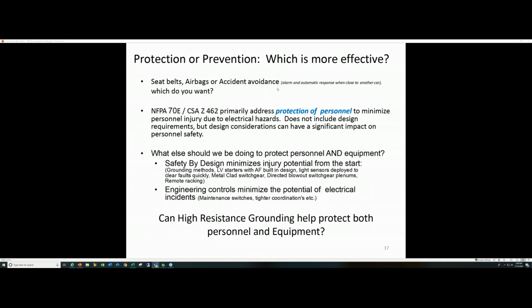And you could also employ engineering controls to minimize the potential of electrical incidents. For instance, maintenance switches, tighter coordinations. We call them maintenance mode switches, that you would activate if you were interacting with the equipment and taking it to a lower instantaneous current while you're interacting, so the incident energy is reduced. So that's something you can do. And most of you guys are familiar with all of this. The other thing that can be done is, well, what about high resistance grounding? How can that help protect not only the employees, that guy on Christmas Eve and his family, so he got to go home on Christmas, and also protect our equipment, which means that we're viable as a company making a profit.